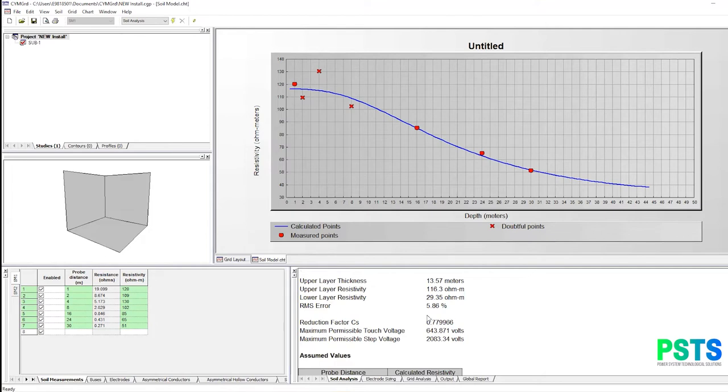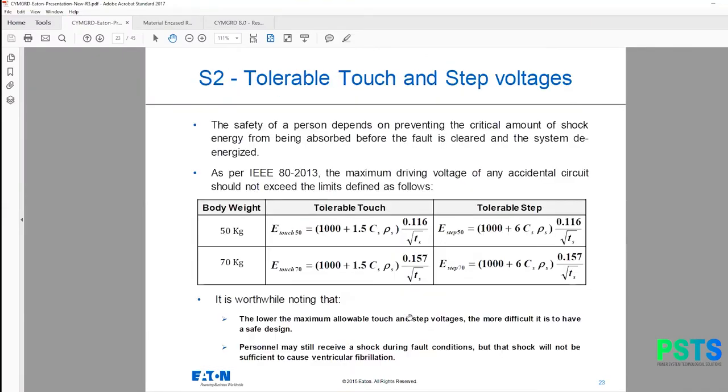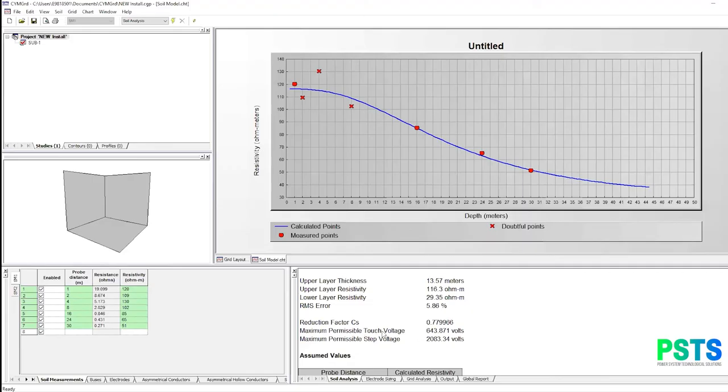My reduction factor, remember I told you there's a derating factor CS, which is this one, is being computed now here. CS is computed for you now. Rho S is known, CS is known, because rho S is a surface, so we can compute the step and touch now. And that is why the program was able to give you maximum touch potential of about 643 or 644 volts.